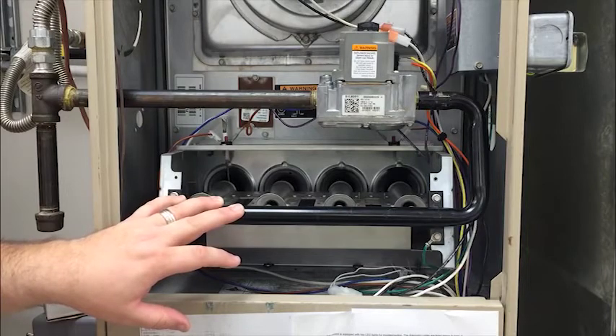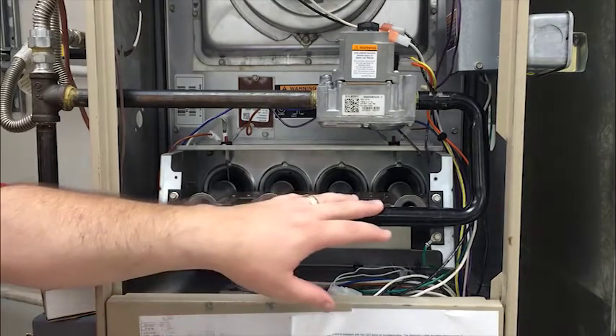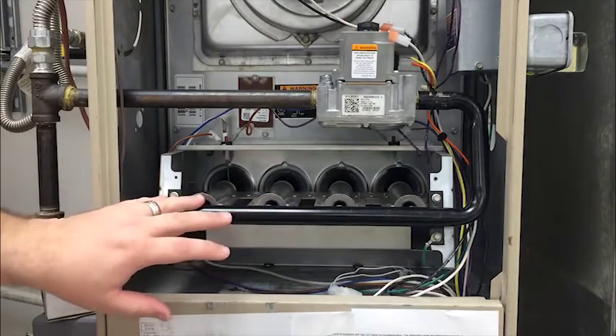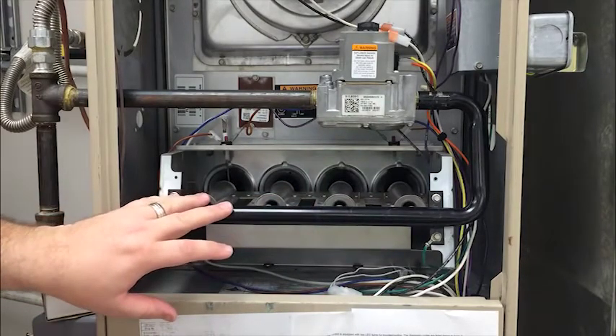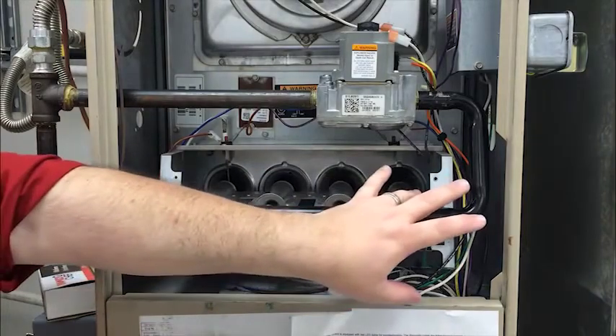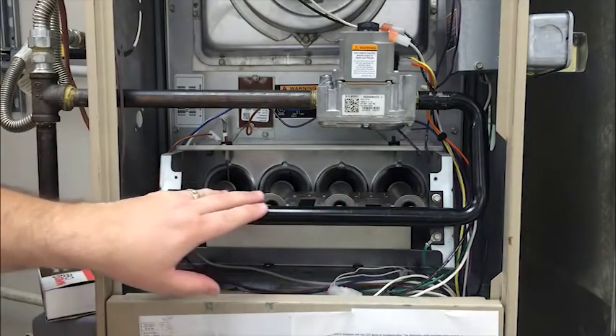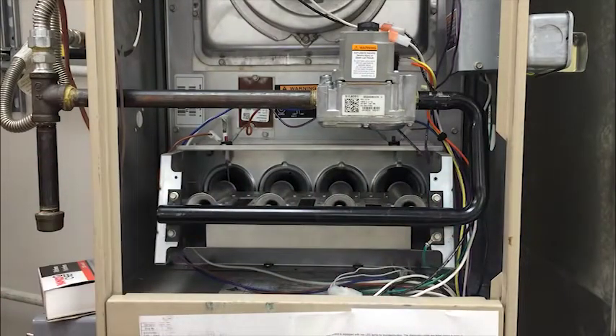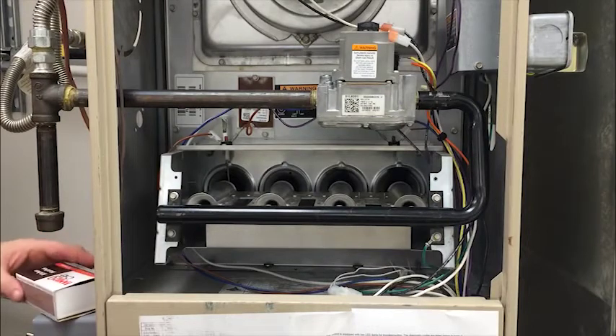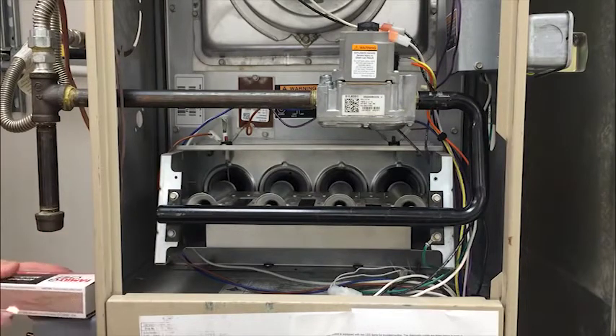When we test a heat exchanger that doesn't have a crack, there should be no visual sign of the flame moving, pretty much at all. So let's go ahead and inspect this furnace, starting from this end, and work our way across to see if we can visually see what happens when a heat exchanger is cracked using the static pressure test.